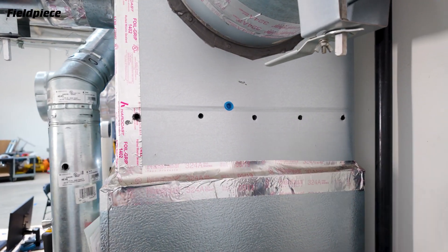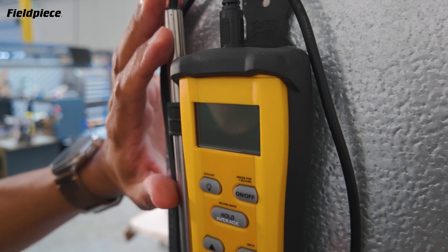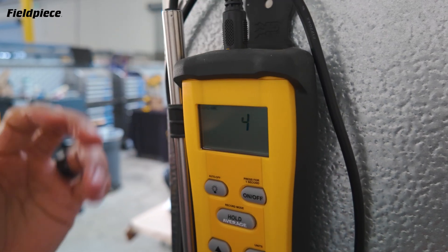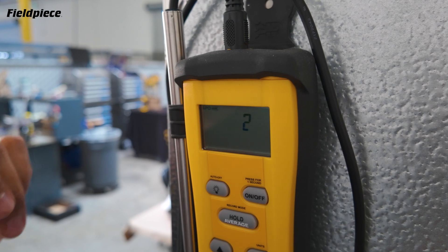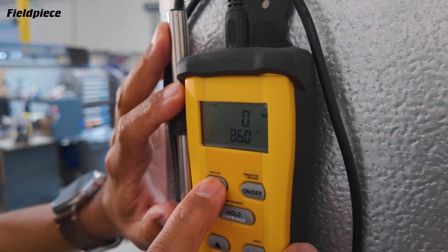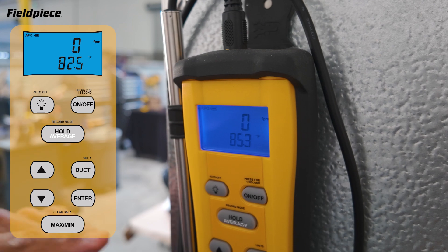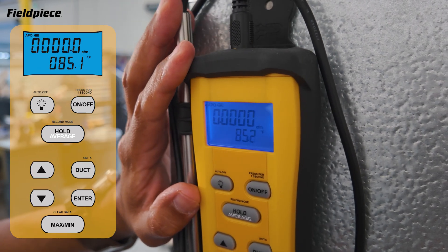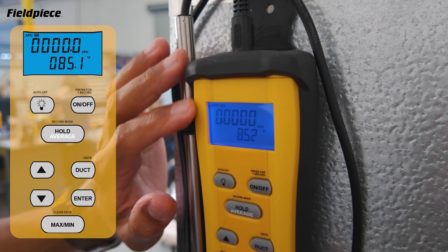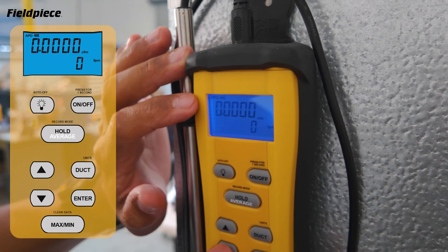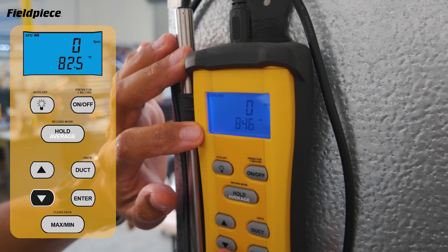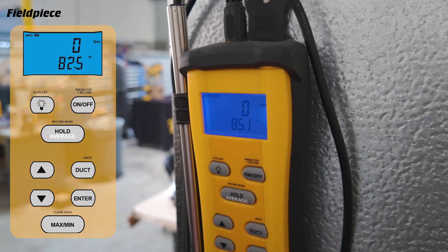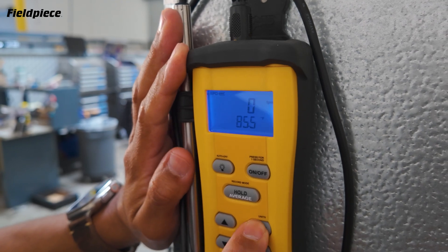Now that we have our holes correctly positioned in the duct, let's set up the STA2. First we power it on — it goes through a quick warm-up period of about five seconds for the hot wire sensor to warm up. Once it's on, the display shows feet per minute at the top and temperature on the bottom. I can use the arrow buttons to toggle between CFM on top and temperature on the bottom, or CFM on top and feet per minute on the bottom. To measure CFM, we have to set the duct size, so we press the duct button.